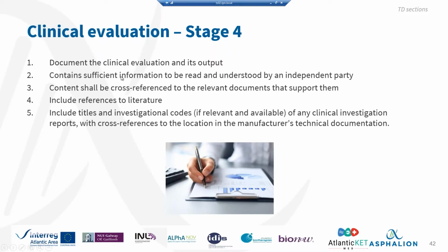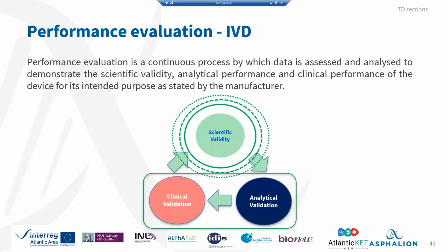And last, it should include titles and investigational codes if you have performed these clinical investigations. Obviously, this depends on the kind of device, because there are devices that do not require clinical investigations. It depends on the device. Okay. And this clinical evaluation report will be included within the section of validation and verification of the device.